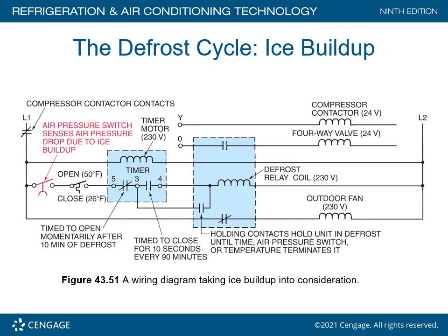Defrost cycle with ice building up. Okay, the air pressure switch senses the air pressure drop due to ice buildup on the outdoor coil. Notice that it is in the open mode. Notice that the thermostat there opens at 50 degrees, closes at 26. Time to open momentarily after 10 minutes of defrost.